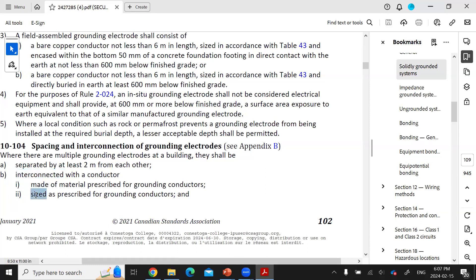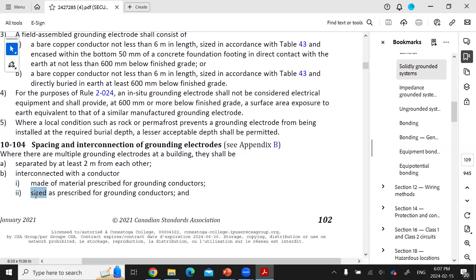Sized according to grounding conductors means they must not be smaller than number six if they're copper or number four if they're aluminum.